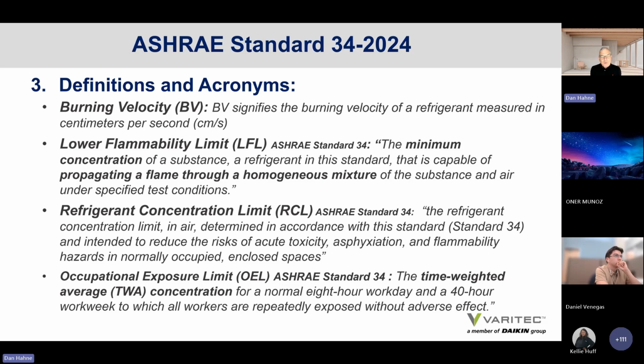An understanding of refrigerant concentration limit is necessary. The refrigerant concentration limit is determined in accordance with this standard, Standard 34, and is intended to reduce the risk of acute toxicity, asphyxiation, and flammability hazards in normally occupied spaces. And then an understanding of occupational exposure limits is another term to understand for the standard. It is the time-weighted average concentration for a normal 8-hour workday and a 40-hour work week that all workers would be repeatedly exposed to.